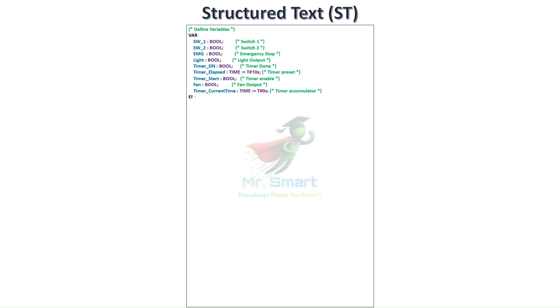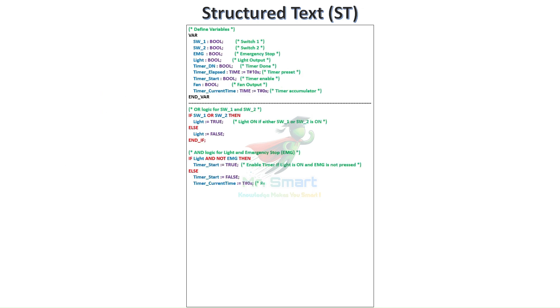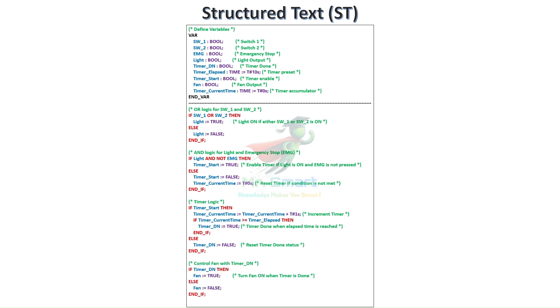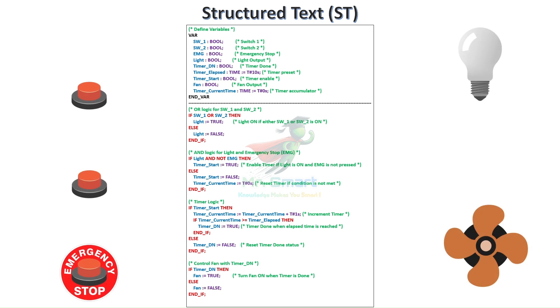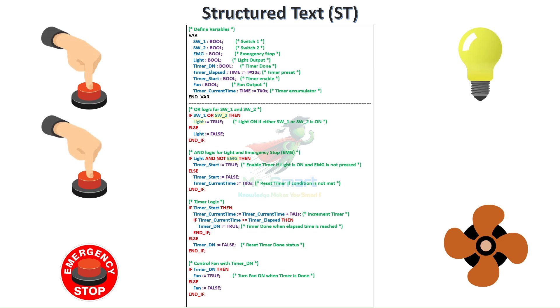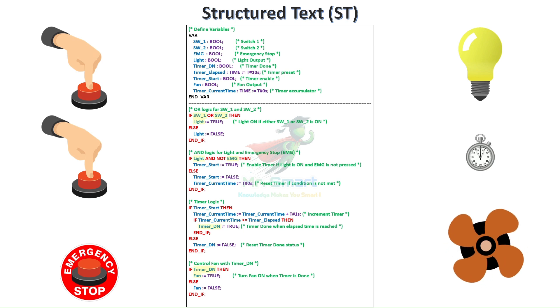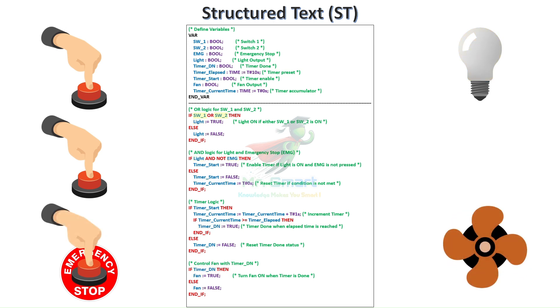Structured text is a high-level programming language that feels like traditional coding in Python, C, or Java. It uses structured commands to create logical operations, loops, and calculations. With its ability to handle complex data, it's perfect for tasks like advanced mathematical operations, data logging, and communicating with external systems. While it requires a stronger programming background, its power and versatility make it a favorite for seasoned programmers and engineers.